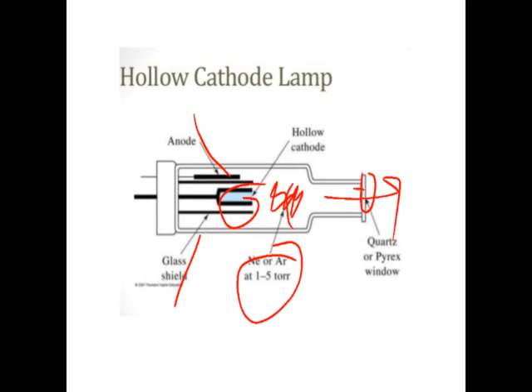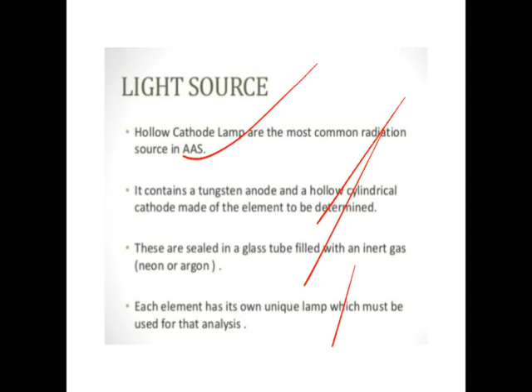The hollow cathode lamp is the most common radiation source. The anode is tungsten. The hollow cylindrical cathode is the cathode. It is made up of the element to be determined. They are sealed in a glass tube filled with an inert gas like argon or neon, and each element has a unique lamp which must be used for the analysis because it is made up of the element to be determined.